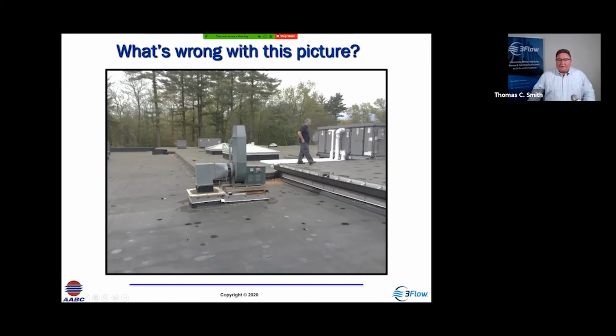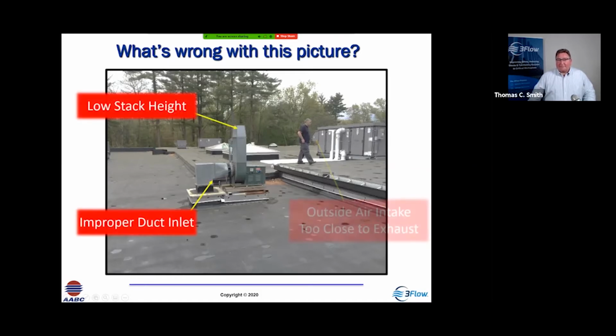And so we know that this fan is probably going to lose about 20 to 30% of its efficiency because of the inlet connection not being appropriate and not getting good flow into this fan. So that's an inefficient inlet that's going to cause poor performance of the fan, which is going to require more energy in order to achieve the desired flow rate. And that's what I meant by an improper duct inlet.